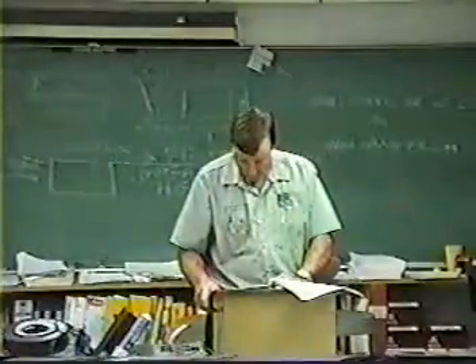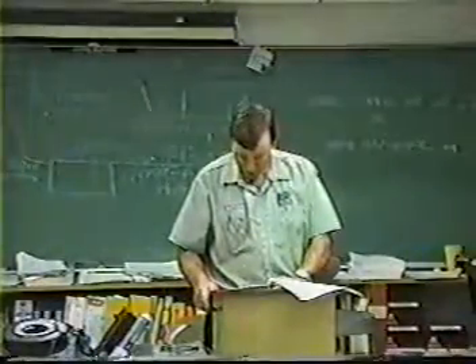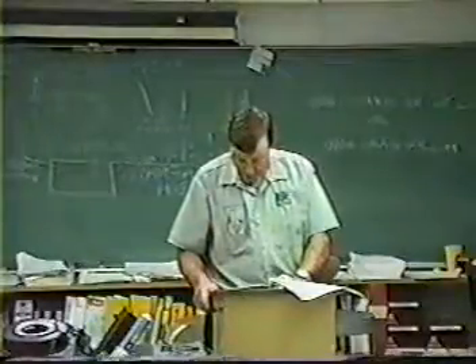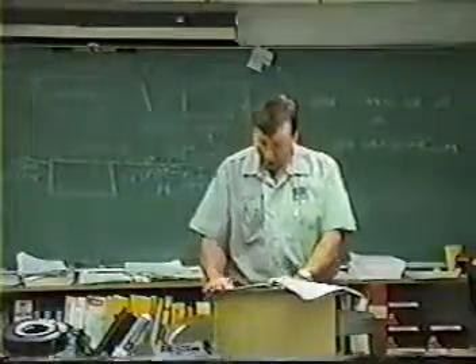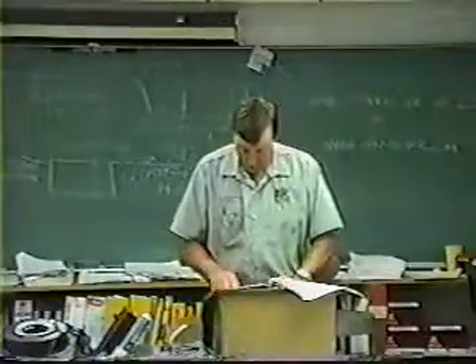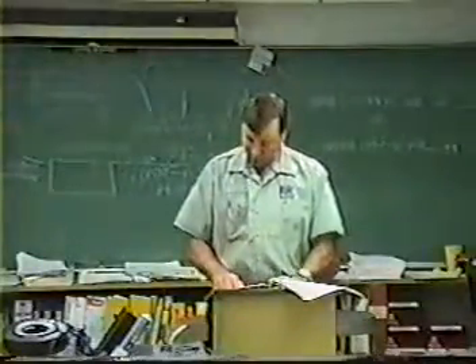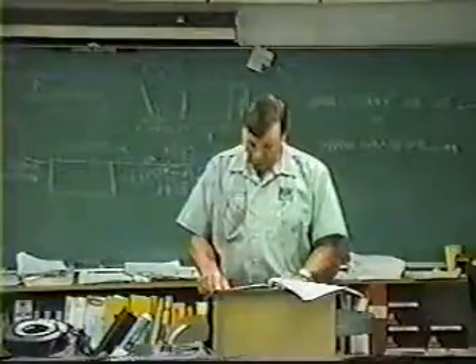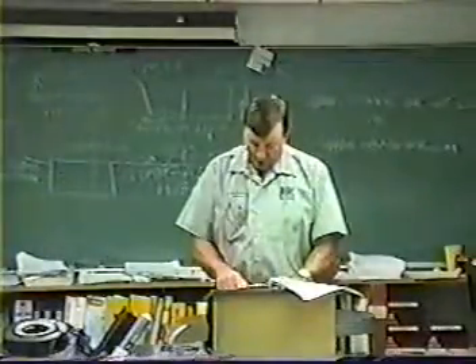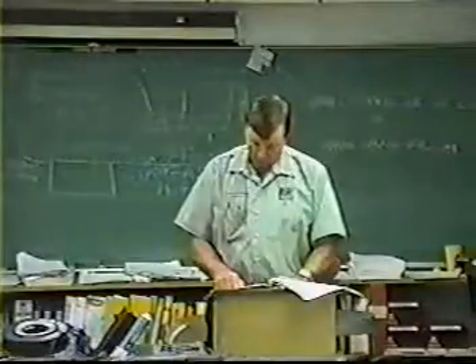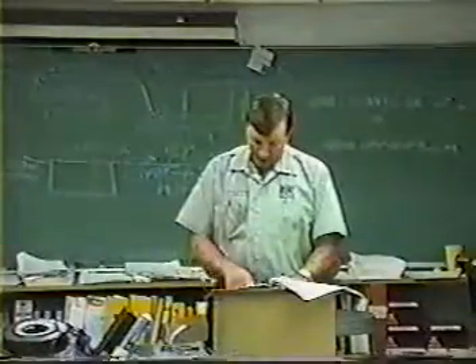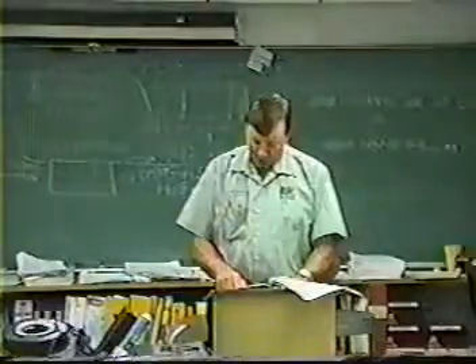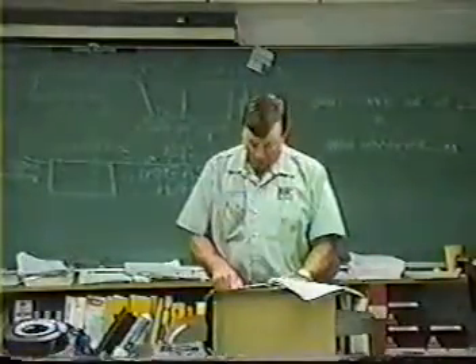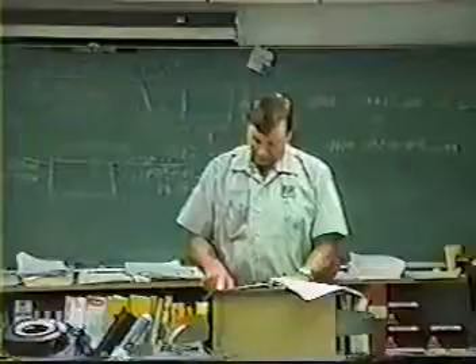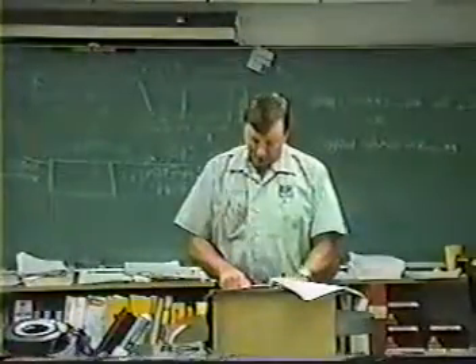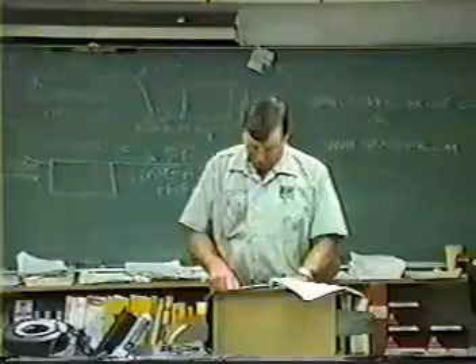moving on down to, let's see, substitute oils. Moving down to blends. Some of the, last paragraph, some of the blends are called ternary, which means they're three-part blends. Ternary blends will leak from a system at different rates because of the different vapor pressure of each component of the blend. It's on refrigerants. The variance in the boiling and condensing temperatures of the component refrigerants is called temperature glide. That's going to be a test question. Because of this, the proper method of charging a blend is to weigh the refrigerant into the system high side as a liquid.